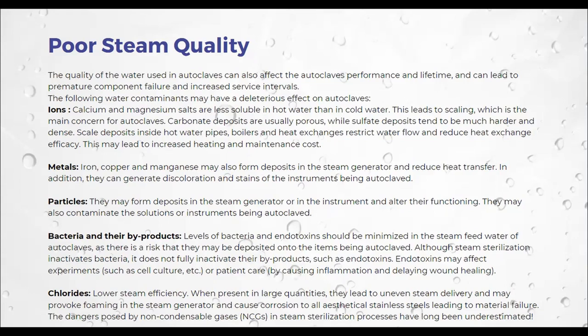And then the last thing is chlorides, which we get a lot in the field lately, as everybody is pouring chlorides into the tanks lately. It lowers the steam efficiency when present in large quantities. They lead to uneven steam delivery and may provoke foaming in the steam generator and cause corrosion to all aesthetical stainless steel, leading to material failure. So it means even the stainless steel of the autoclave could corrode, which would shorten the lifetime of the autoclave, including the instruments.